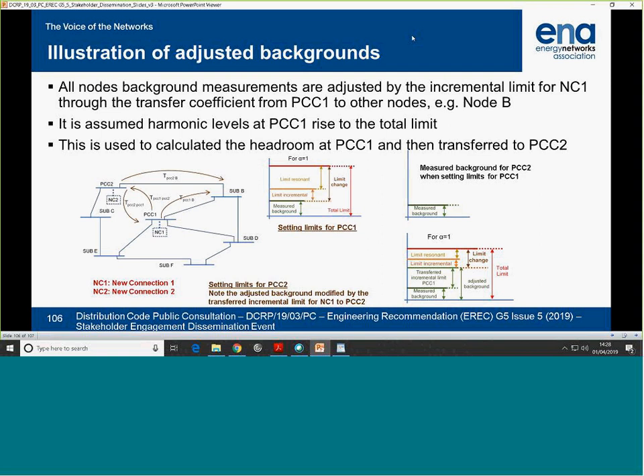So what happens when you get a site with two feeds at two separate points on the network? That's it. The site would have two separate limits. You have one site, so take for instance 33 kV. So I have it going to there, NC2 and NC1 are my two main connections so that I get a secure feed to my site. Where are we with the limits with that? How would you apportion to the site?